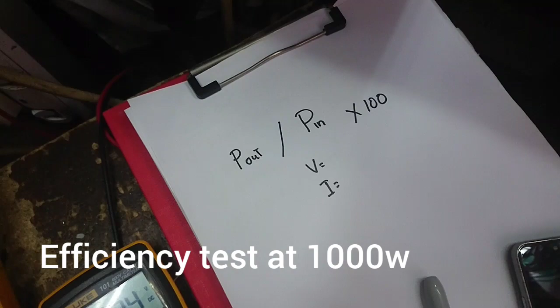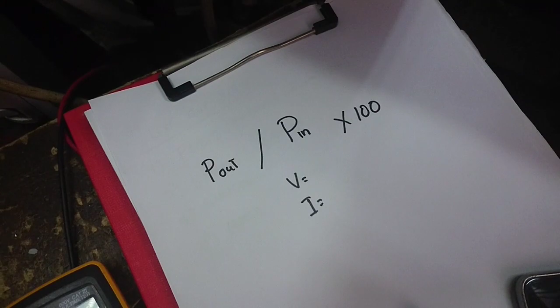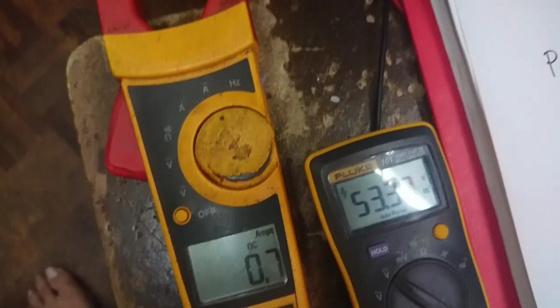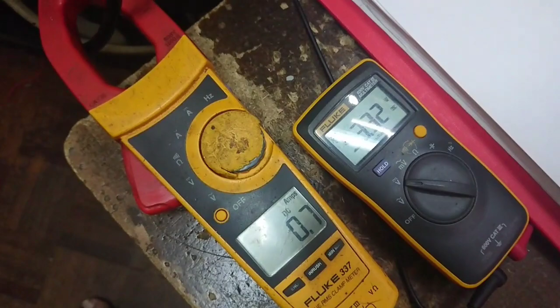Okay, I use the normal formula, P out over P in times 100. For P out I just use the kWh meter, and P in I measure manually using a Fluke tong meter and multimeter. Now the standby is only 0.7 amps. 0.7 amp is good news for a 7 kilowatt low frequency inverter. Very efficient, more efficient than a high frequency inverter in standby mode, you know. 7 kilowatt, 0.7 standby.